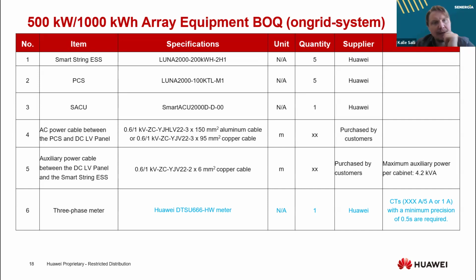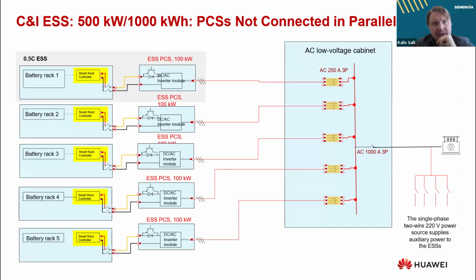Can you go one slide back? In this case, if there is a 100 kilowatt unit, you recommend 250 amp fuses in those? Yes, the PCSs will have a discharge apparent power of 120 kVA at maximum for short periods. For that, we have a 173.4 amps breaker in the data sheet. But of course, if you want to limit it to only 100 kilowatt and not exceed 120 amps for 400 volt, then we can have a 155 amps breaker. But of course, you have to take into consideration the short circuit current.